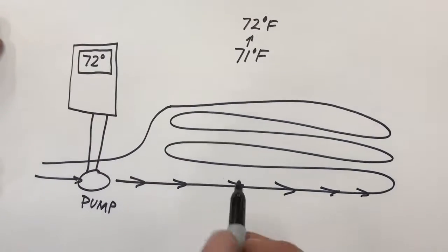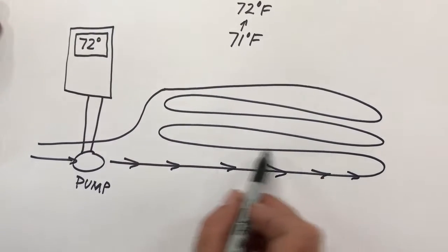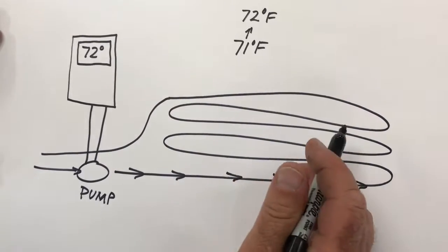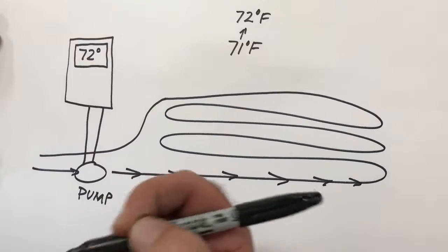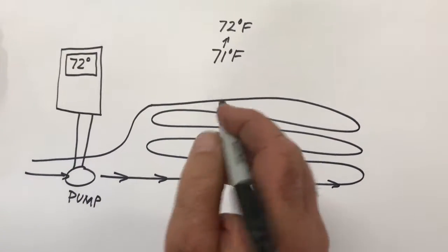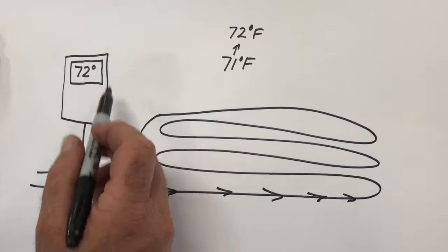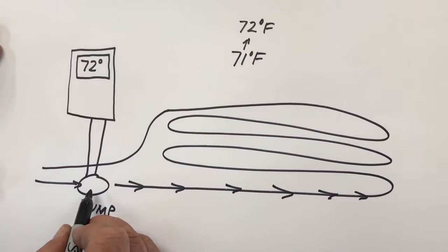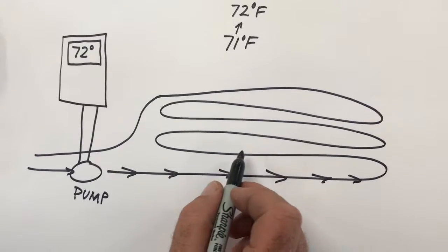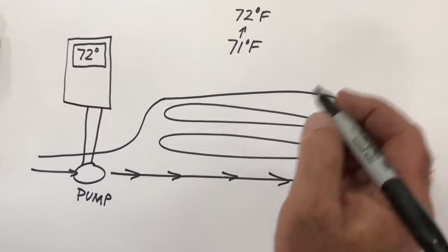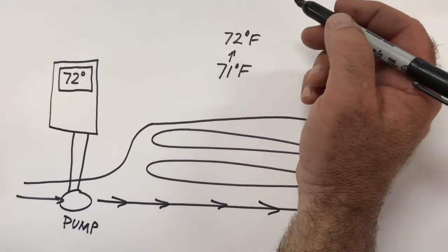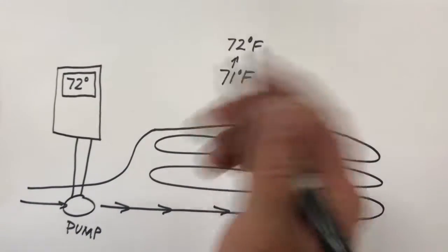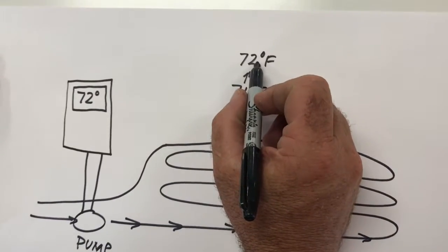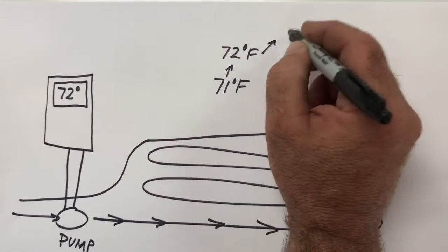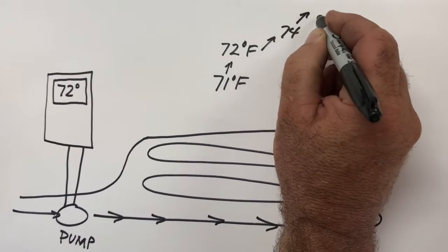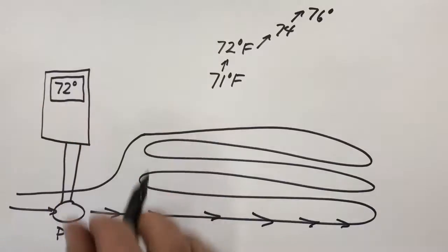The problem with hydronic systems is that there's still going to be a considerable amount of hot water sitting in the floor. And depending on the outside temperature and depending on how fast your room loses heat, it can still continue to heat the room. So a normal thermostat, all it can do is shut off the pump, but it can't control how much extra heating happens. So it's not unusual, especially during the springtime when you've got a lot of solar energy coming in windows, that 72 degree set point could rise to 74, 76 degrees, something way hotter than the set point.